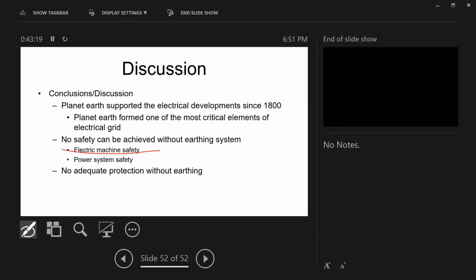Because like I said, there are two types of protection. Number one, high fault current; number two, low fault current. Both of them require earthing. How do you achieve low fault current? By putting in a neutral earthing resistor, an NER system.